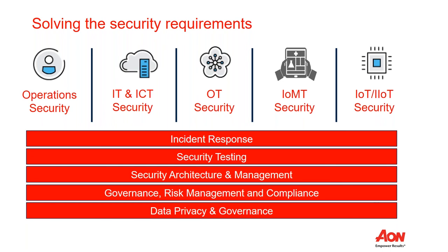Once the risk management framework I've just described is in place to operate within, the first stage for developing a new medical device securely is following common practices to develop a defense-in-depth approach, and this is from the document itself. Just to talk briefly about defense in depth - this means having multiple security controls that are usually layered to avoid any single point of failure. But if one does fail, then there are other controls that can help pick up the slack, if you like, and potentially mitigate risk further.